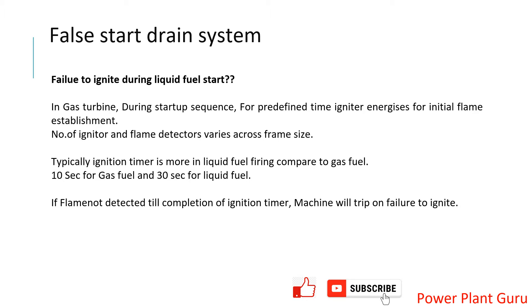False start drain systems are designed to de-risk the gas turbine from a potential risk of fire or explosion hazard, which may occur due to remaining or residual fuel accumulation in the gas turbine from the previous attempt of starting the machine. Let us understand in detail how this system works.